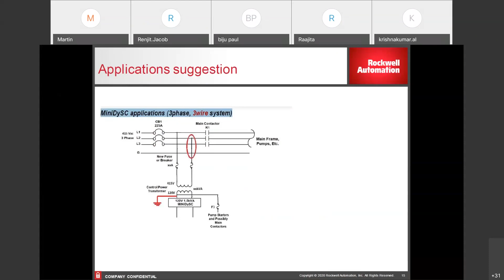Now you can have it with a line-to-line configuration if the secondary is not grounded. There are some cases wherein the isolation cum step-down transformer secondary has been grounded. In those cases, you can use a line-to-neutral type of configuration. If it's an ungrounded secondary on the 120 volt or 110 volt side, then you can use even the line-to-line configuration. Absolutely, these kinds of flexibilities are available.